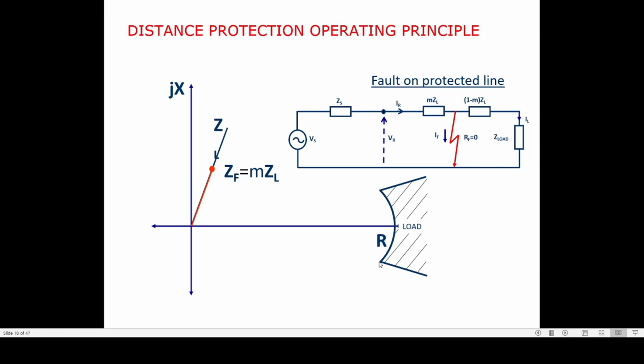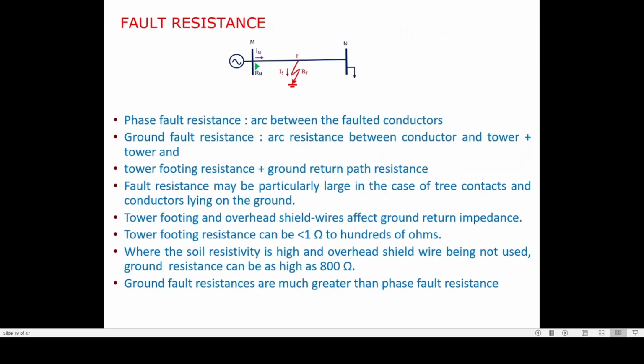Now, this side basically represents the load, because when the system is running, the total current in the system is much lower than the fault current. That means the impedance measured by the relay during those times will be very high, and that impedance may lie somewhere outside, or somewhere far away from the impedance measured by the relay during the fault time.